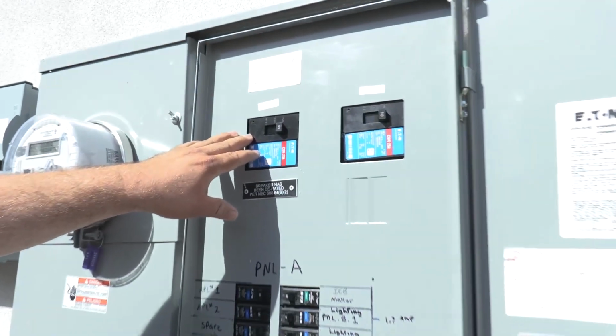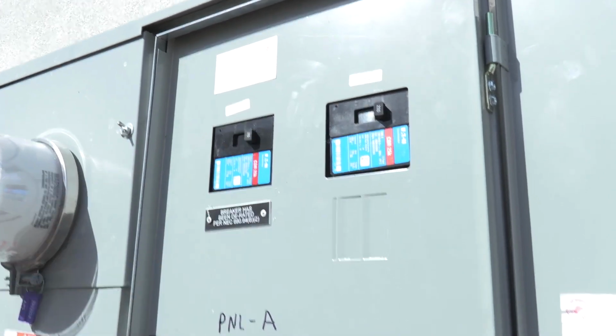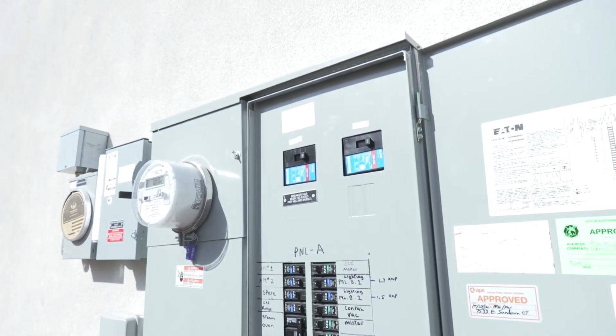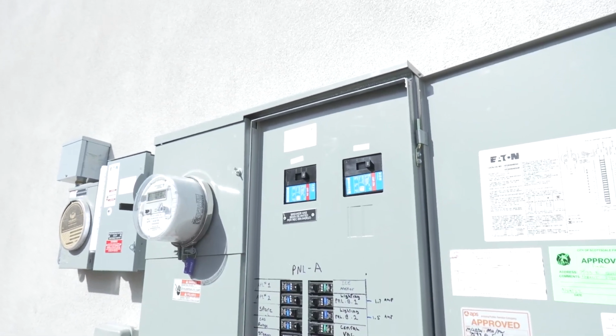We need to put a 175 amp breaker in here to allow us to be within that 240 total amps going to the bus bar. 175, 60, we're at 235. So technically we could go 5 amps bigger if they ever wanted to increase it a little bit.